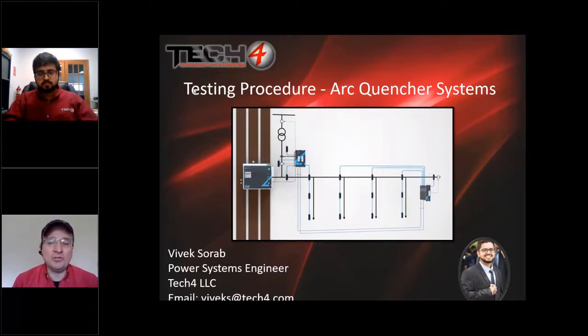And the second reason why arc quencher resettability is important is because like any electromechanical device, such as a circuit breaker, the clearing time, or in this case, the closing time of the arc quencher device should be periodically validated. And of course, as Vivek will cover in the upcoming presentation, we recommend that the arc quencher systems be maintained at the same frequency that the facility or plant maintains their circuit breaker devices, either following NFPA 70B guidelines or Factory Mutual maintenance recommendations. A typical testing frequency in a normal environment for a circuit breaker would be once every 3 years, and if that's the policy you follow, then we recommend you test the quencher system, as Vivek is about to detail, once every 3 years.